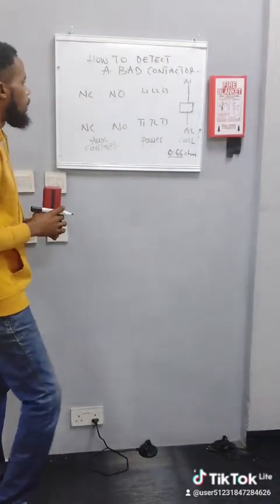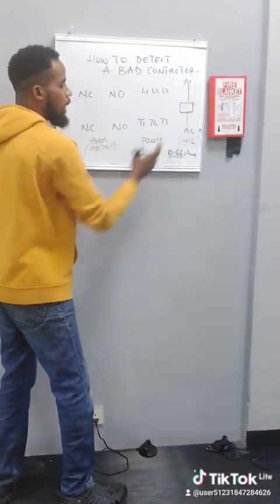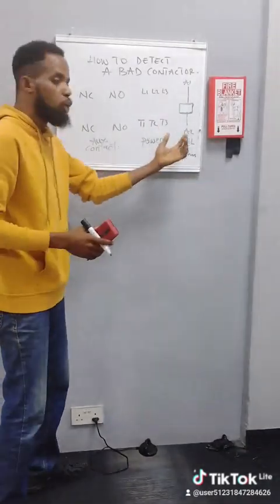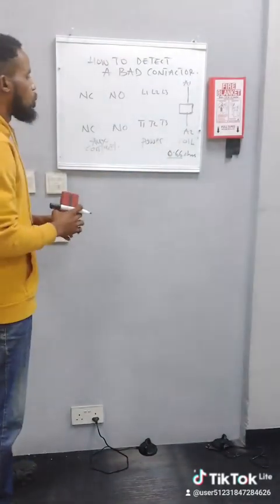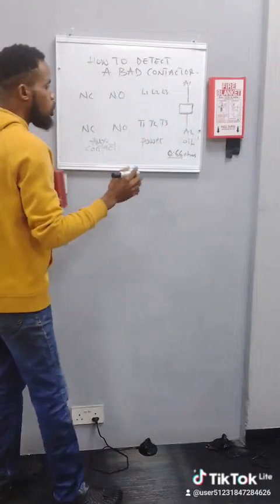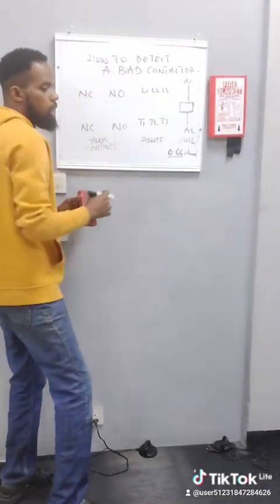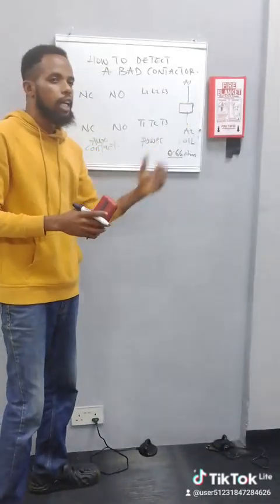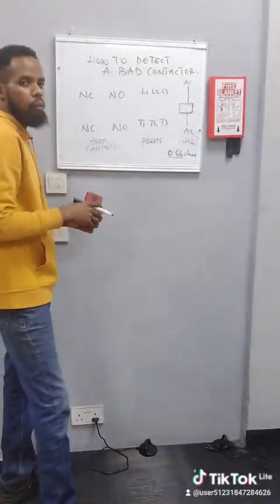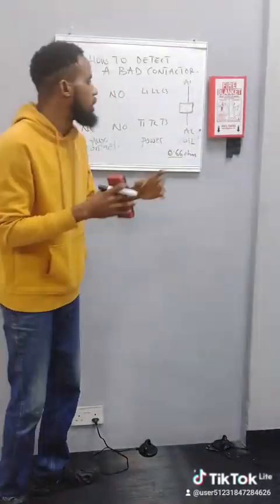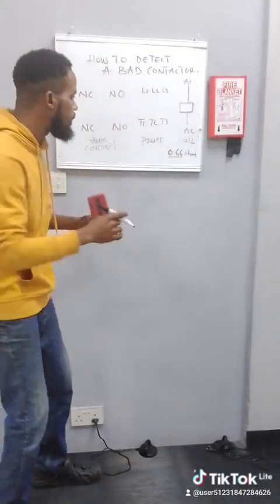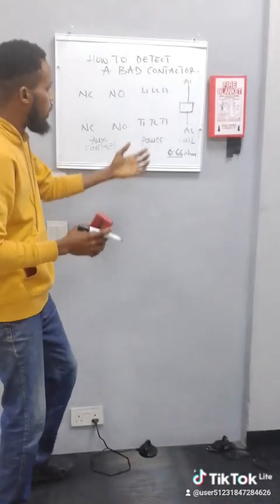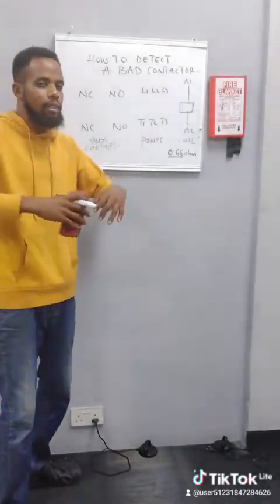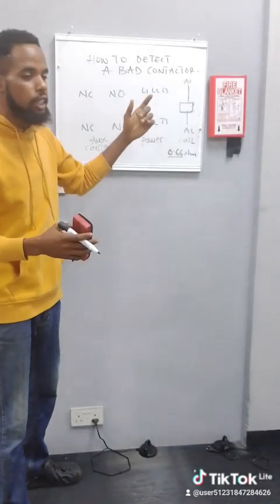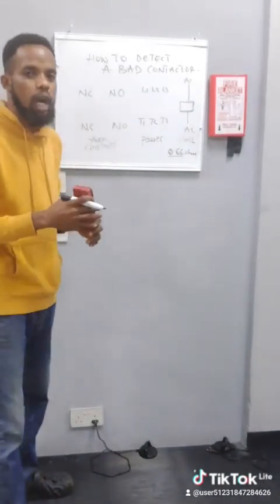Now, if our contact side is okay, maybe when we troubleshoot it we get 0.66 ohms, then the contact side is okay. So what will be the other cause of the contactor problem? Number 2 is the voltage that's supposed to energize this coil; the voltage is very low. The voltage cannot energize because each contactor has a different specification. Sometimes we have a DC coil in the contactor, and sometimes we have an AC coil.